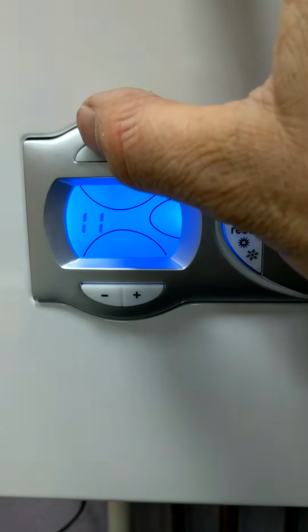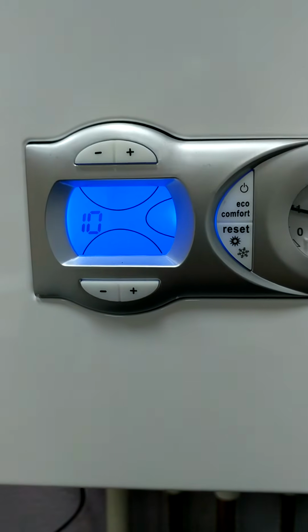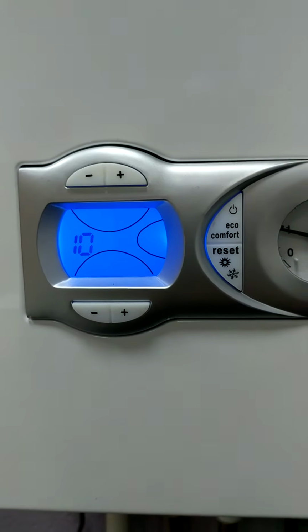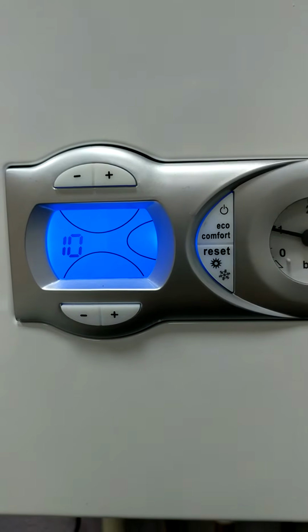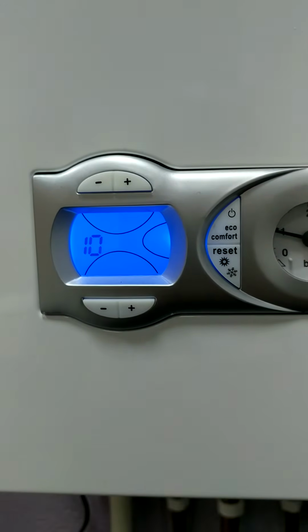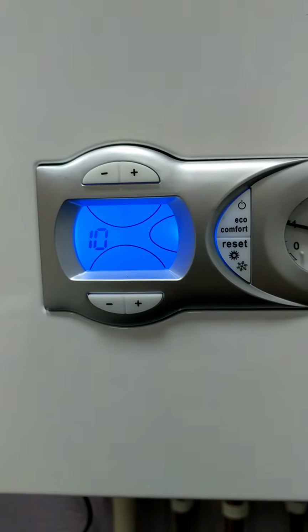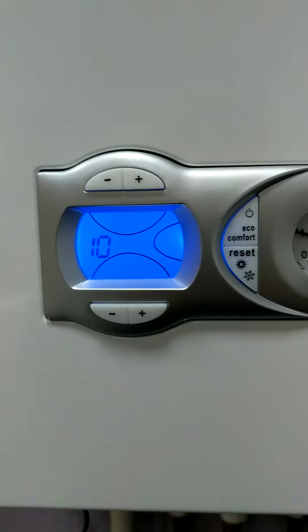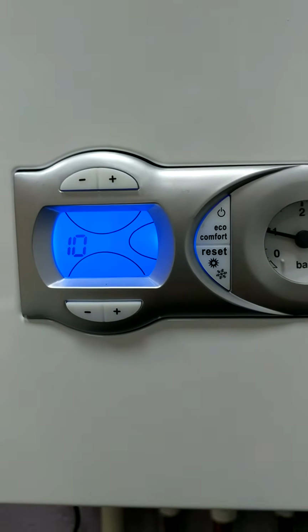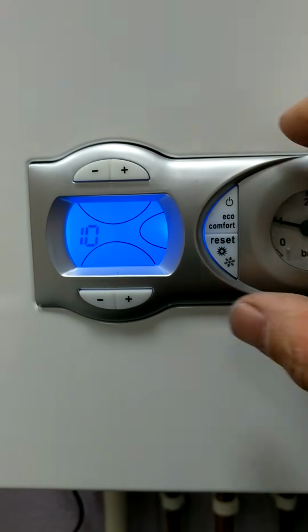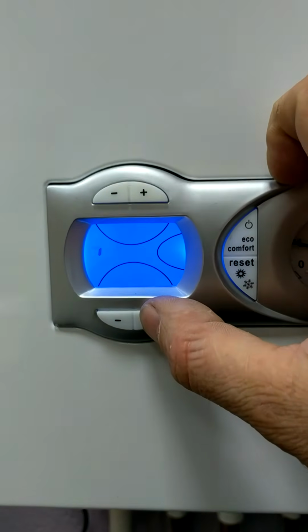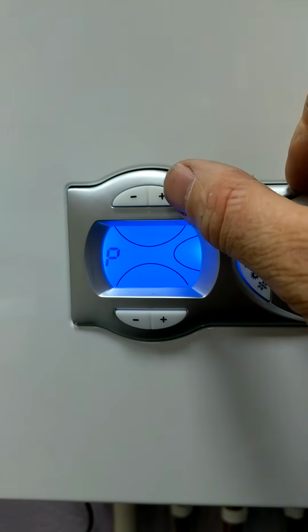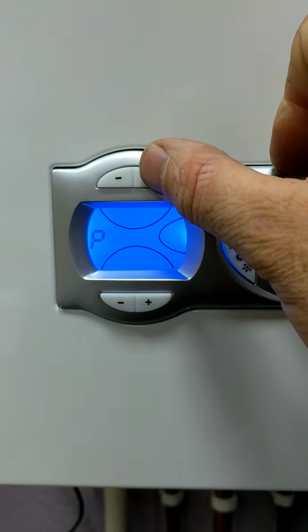And all these parameters just make that boiler work just a little bit better. This is what you can do on a service. If you've repaired it, changed the circuit board, or it's a brand new installation, you can set the boiler up, and you might not get a lot of these weird calls from the customer. It's too noisy, it's kettling. Just because you've changed a few parameters and set the boiler up on commissioning, and it doesn't take that long with the video.